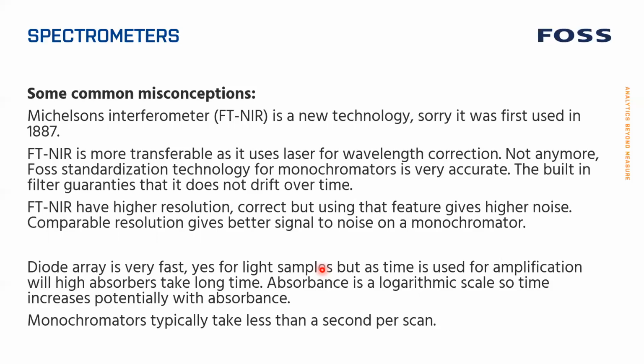Then diode array, it's very fast. It's been pointed out as being much faster than other spectrometers, and that is true when you have light samples, but it's using time as an amplification. So if you have something that's really dark, it will actually take a long time. And absorbance is a logarithmic scale, so when it goes from one absorbance unit to two absorbance units, it's a tenfold change in time. And monochromators typically take less than a second per scan.